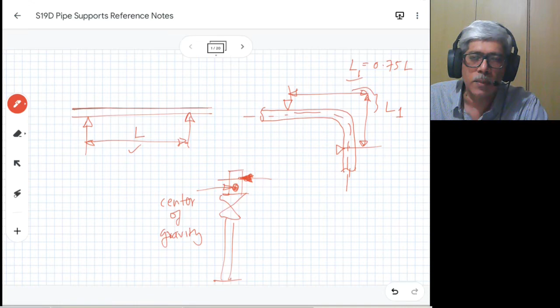So if you are having a pipeline, let's say it's a vertical pipeline, and let's say there is some heavy weight which is provided. If this is your pipeline, because of this weight, the CG will be shifted somewhere to this point. So this is the center of gravity of the pipeline. Then it is recommended that you provide a support which is above the center of gravity. That is in order to make the pipeline more stable. If your center of gravity is below the support point, you will get a more stable pipeline. That is the idea behind this guideline.